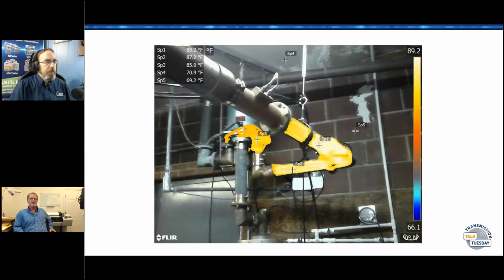Elbows tend to be hot spots. Anytime there's a transition or turn in a line, they can be hot spots. That one you'll notice is a warm spot. Also, where it goes up into the coax switch for the two transmitters and two dummy loads, you've got a warm spot there too. That wasn't a reflection versus emissivity issue - it's actually relatively warmer at that spot.